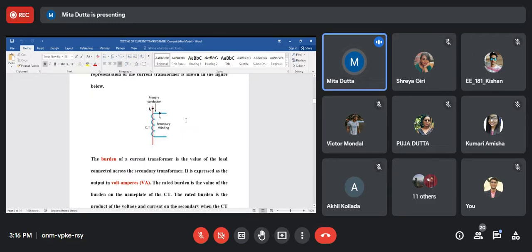No, it will be the rated secondary terminal voltage at rated secondary current multiplied by the rated secondary current. Say we have a 1000 ampere by 5 ampere CT, and we have a 200 volt ampere burden. Then what will be the rated secondary terminal voltage? Yes, so that will be the burden: rated secondary terminal voltage into rated secondary current, not secondary current into secondary terminal voltage. It should be rated.